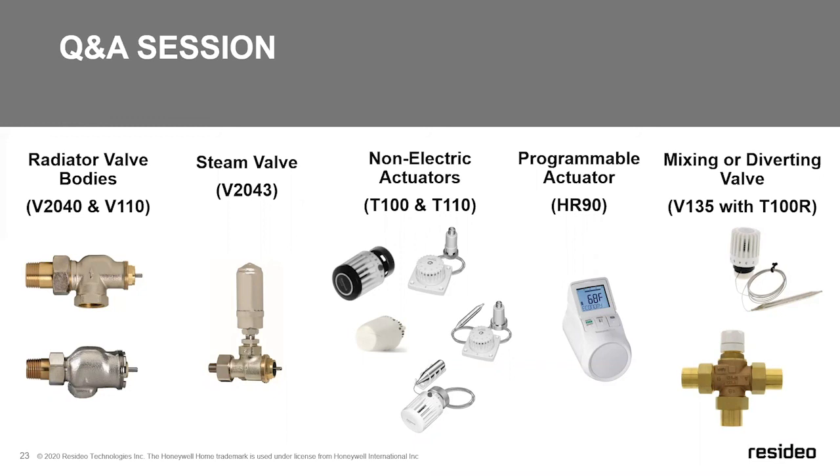So usually we still go back to a central thermostat to kick the system on. Then every radiator is going to open or close as needed, but we have to have that one thermostat set. What I've seen a lot of people do is set that thermostat a little warmer than comfortable. Let's say you want the house to be at 70 degrees. They may set that thermostat at 72, just in case there's one room that's a little cooler, it will still tell the system to come on and it'll have heat available when that opens.